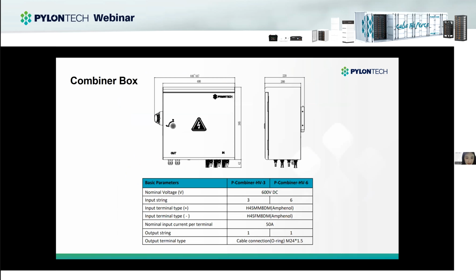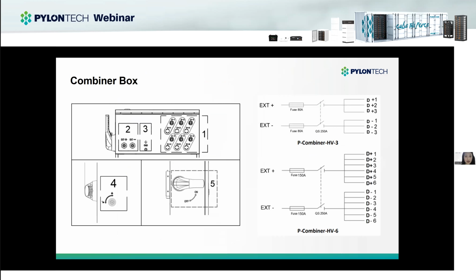We have two types of combiner box. If you have 2 or 3 BMS, you can choose the combiner HV3. If you have 4 to 6 BMS, you can choose the combiner HV6. From this picture, look at the right picture first. You can see that the power cable inside the combiner box is equipped with a fuse to provide safety. And on the left picture, you can see there is a main switch outside the combiner box.